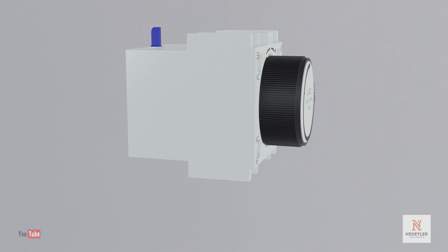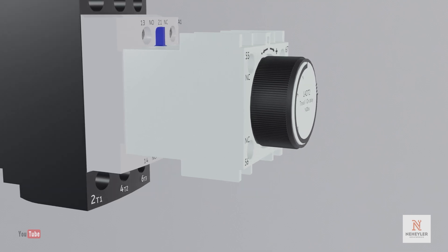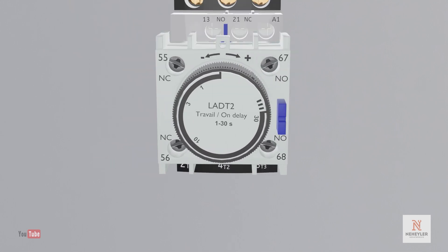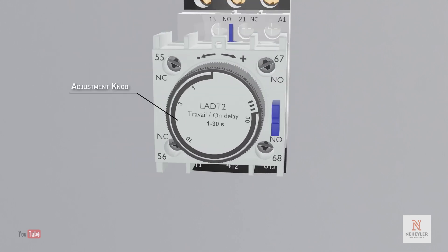To understand better, let's focus on this type of pneumatic timer that is on delay. This timed block requires a contactor for its activation. On the front there is an adjustment knob which we can turn to adjust a delay time between 1 second and 30 seconds.